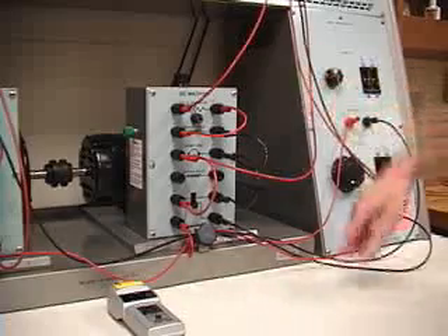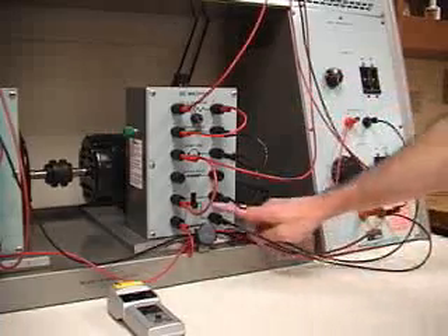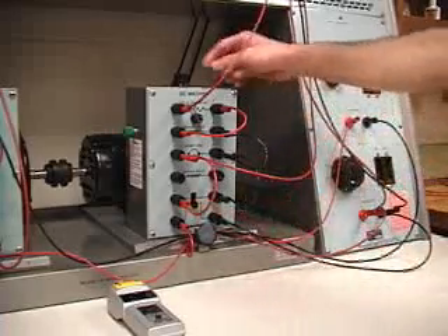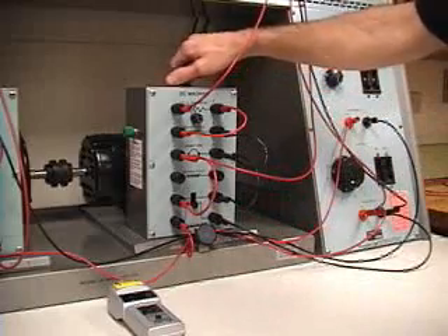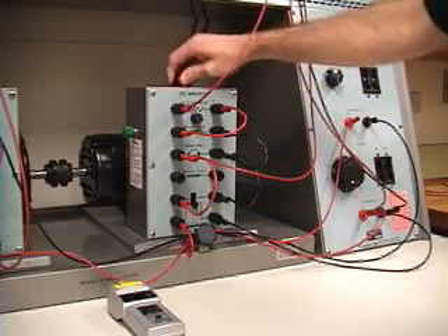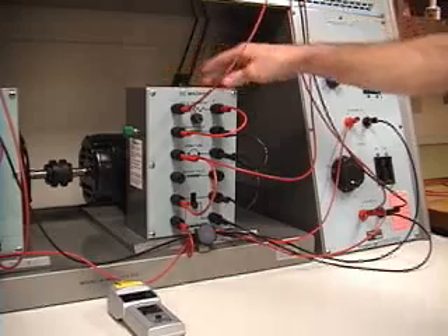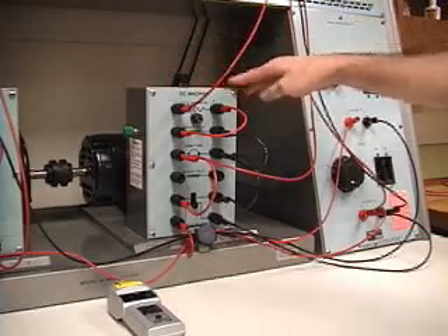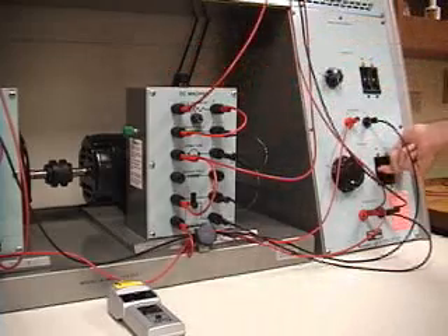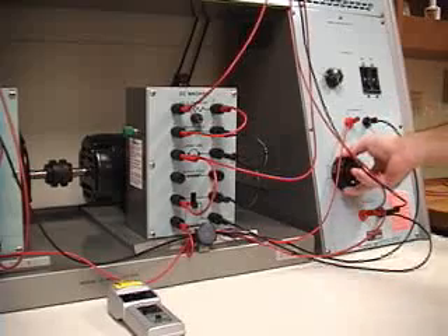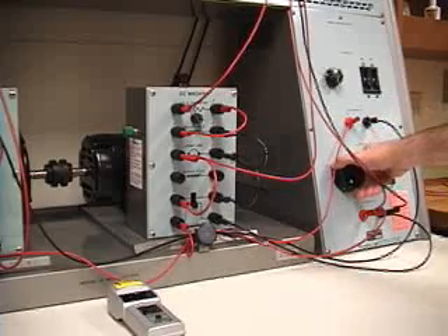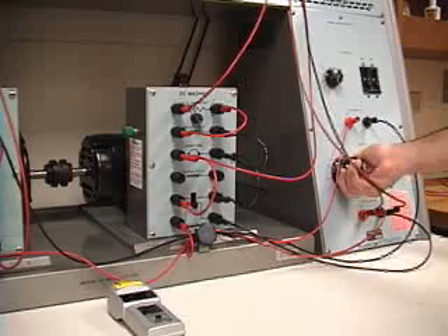First step, important in starting up the DC motor, is have the circuit breaker initially off, have the excitation field rheostat in its minimum position, not maximum, in a motor startup. Our DC power source circuit breaker is on, our adjustment knob is at 0, and we're going to slowly ramp up the voltage until we get rotation.